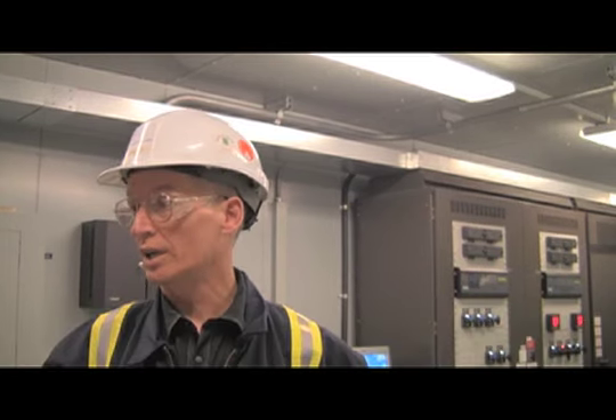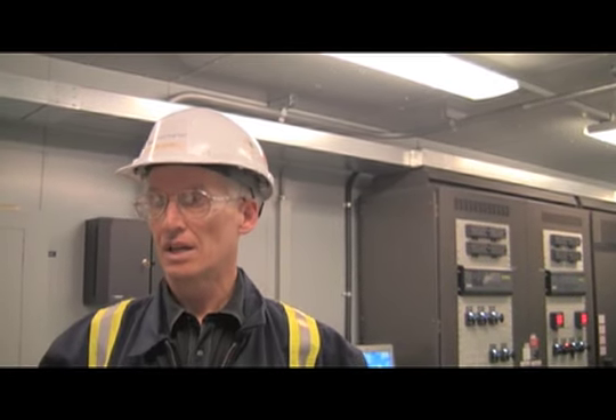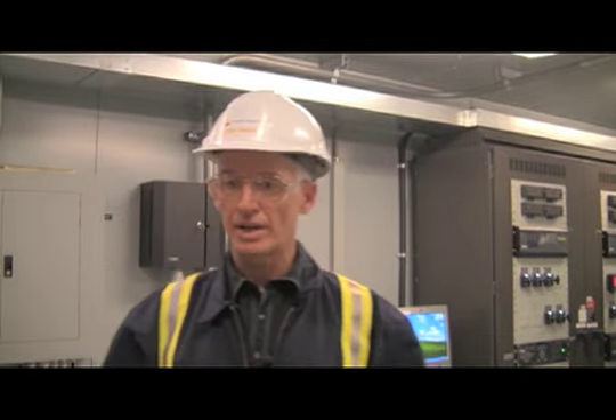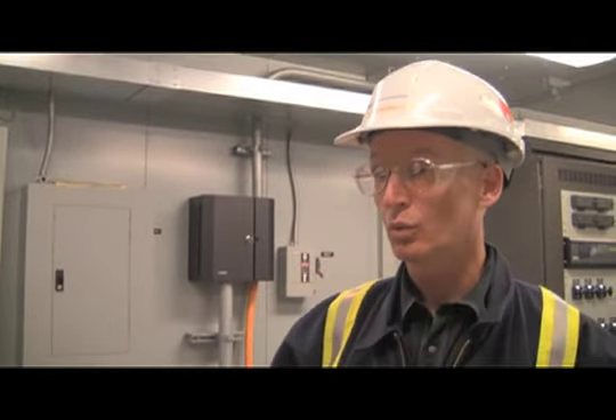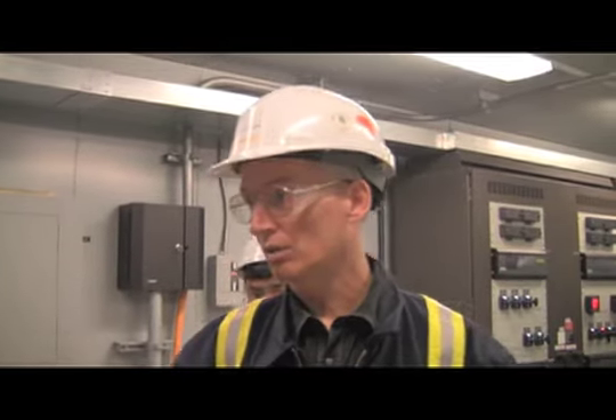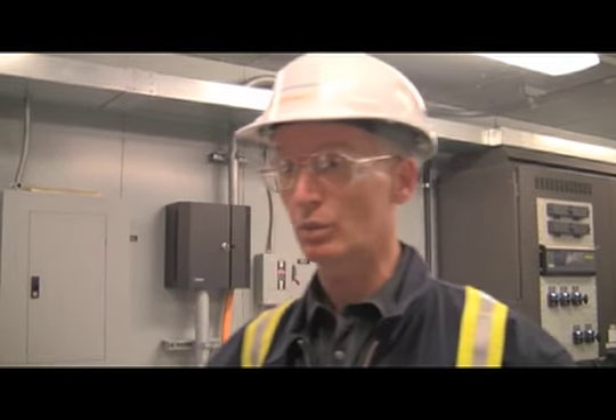Basically, the way the facility is built, it's a 2-on-1 7FA gas turbine with one steam turbine. Each gas turbine is rated for about 190 megawatts. We can run individually. We can run 1-on-1 or 2-on-1. That's the way we run sometimes when we do maintenance. If we need to take one gas turbine out for maintenance, we can still run the other, basically 60% of the facility.